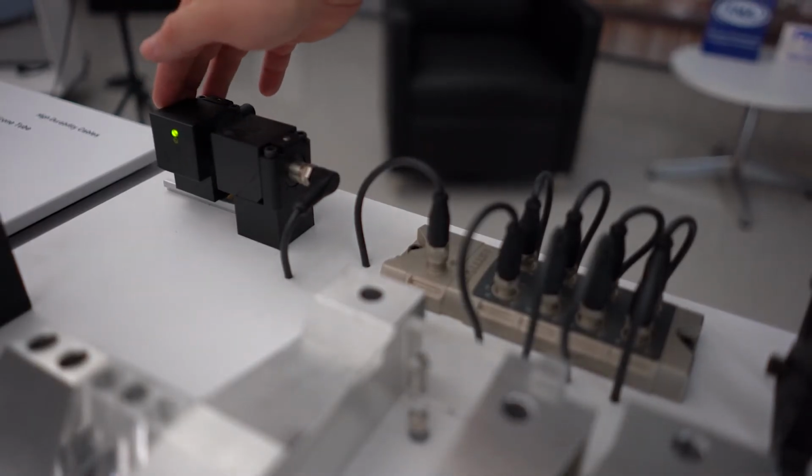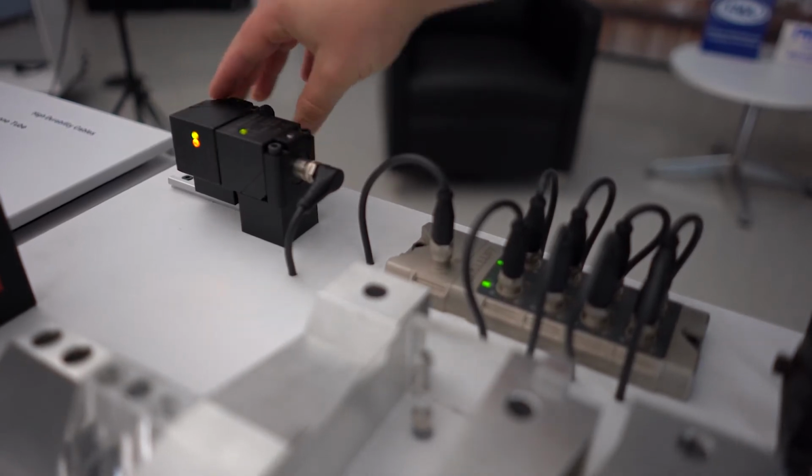How do we avoid that? So Balluff offers this inductive coupling solution, which helps with, first of all, identification on the other side, because you could mount a Balluff I/O Link I/O hub so that you can record its identification number. That can be done easily without having to do the shorts and all those kinds of things. Secondly, with the inductive coupling, there is no physical connection. You are actually passing the data and power across an air gap, a 2 to 5 millimeter air gap. So there is no physical connection, so there is no question of ripping those connectors out. So you have a long-term solution for changing out the dies or tools in your machine without having to go through that downtime.